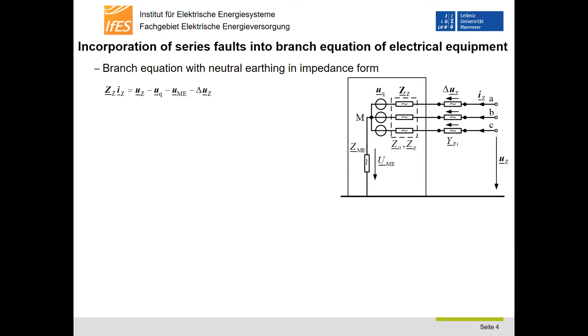Series faults have to be incorporated into the branch equation system of electrical equipment. In the figure, a voltage source equivalent circuit of an electrical equipment with neutral earthing is shown. On the left-hand side, the corresponding equation system is given. Delta UZ are the voltages at a possible interruption at the terminals of the electrical equipment. The fault admittance YF represents the reciprocal of an arc resistance ZF.